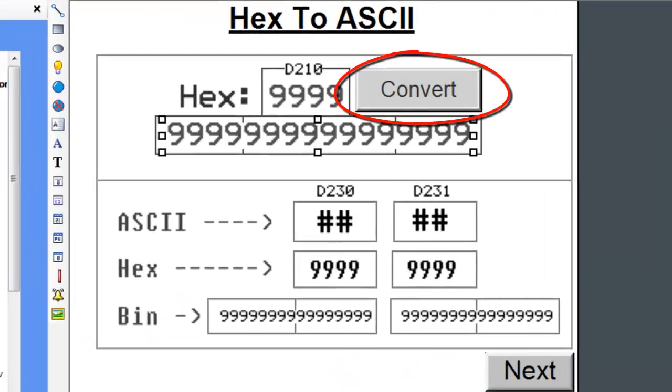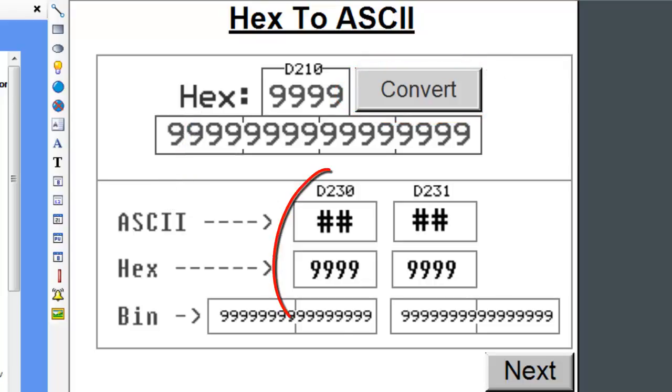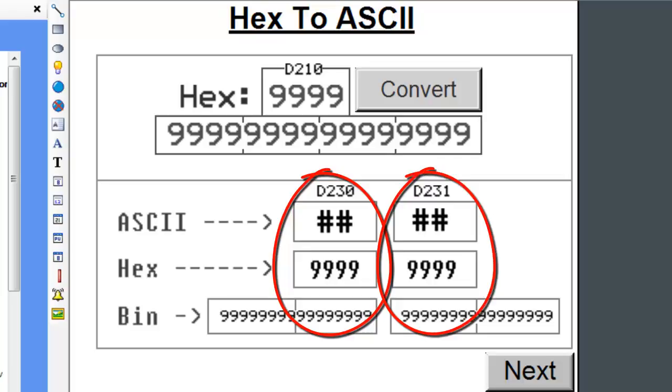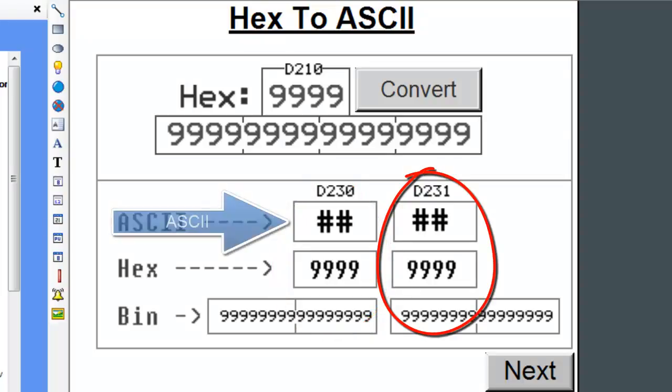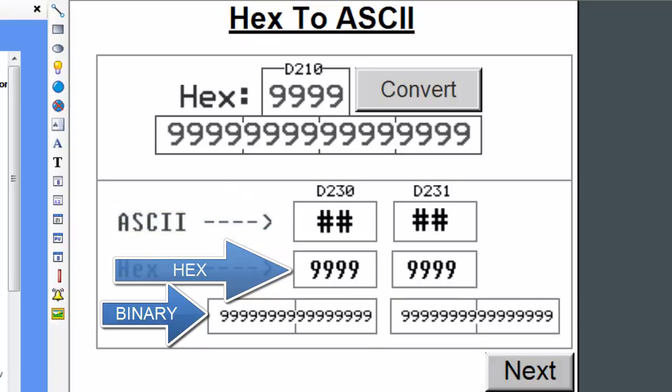The tag address is the same D210 but its data type is a 16-bit binary. When I press the convert button, the hex value is converted into the ASCII value. We are representing the register D230 and D231 in three different forms. In the ASCII form, in the hex form, and finally in the binary form.